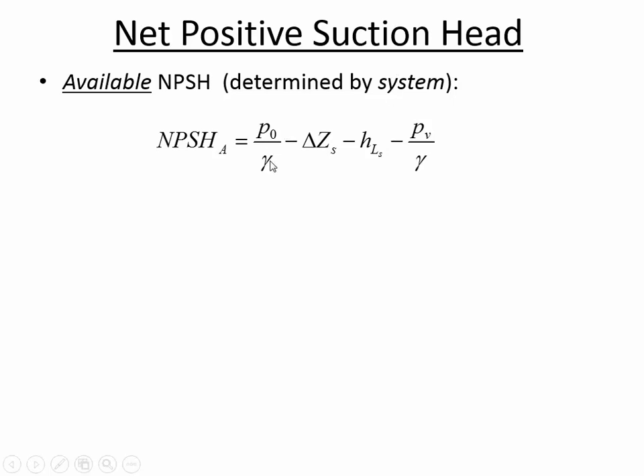And so atmospheric pressure is 101,325 pascals. So 101,325 newtons per meter squared. And the unit weight of water is 9810 newtons per meter cubed. And so what that tells us is that at the maximum, even if there were no energy losses due to pipe friction, if all you are doing is a delta Z, about 10 meters is the most that you could lift the water on the suction side before you have a risk of cavitation.